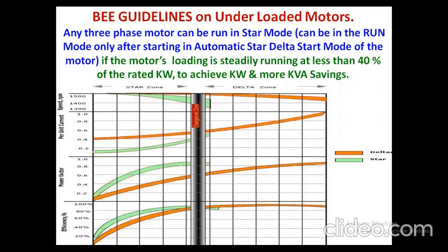In that case, instead of fixing a VFD, which is a costly solution, we can go for an automatic delta to star converter. It's an electronic EEPROM controller. Once it is fixed, provided the motor running kilowatt is less than 40% of the motor rated kilowatt, a motor can be run at 230 volt instead of 400 volt. Still, we can achieve savings of almost 8 to 10%.